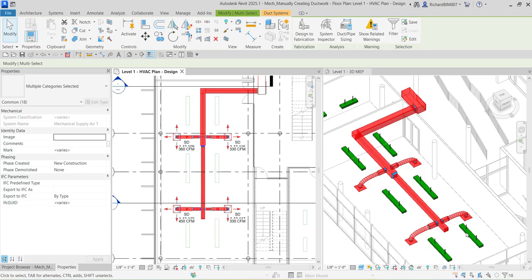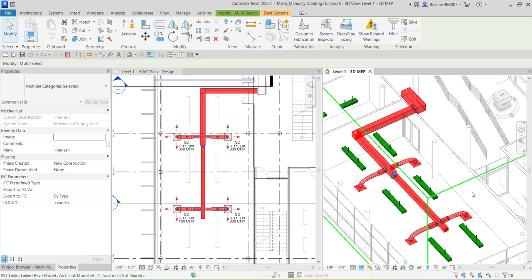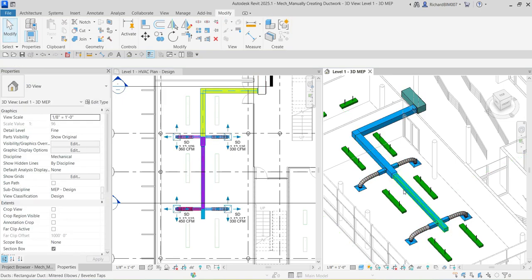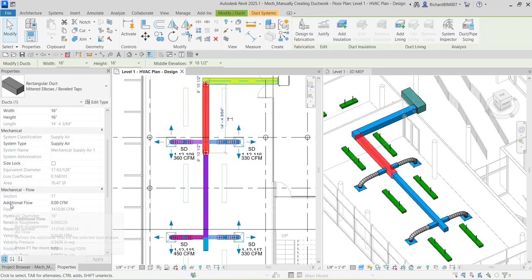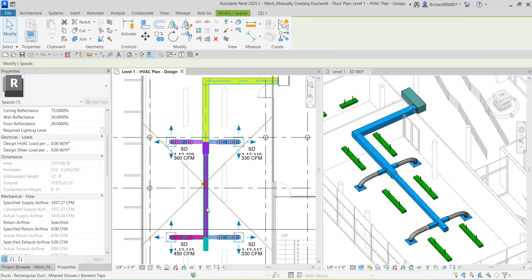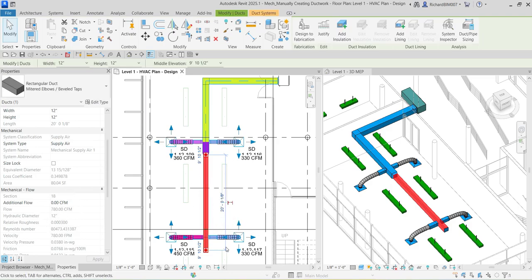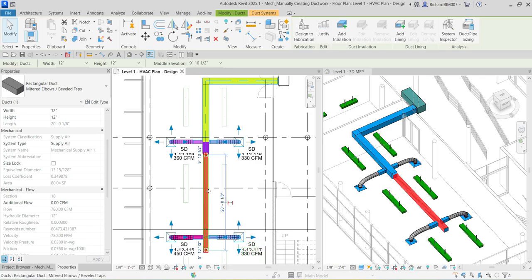The duct is now properly sized. Select Modify to deselect. You can verify by clicking the main duct — the flow is still 1470 CFM. Clicking the downstream duct segment shows only 780 CFM, because it supplies only two diffusers: 450 plus 330 equals 780 CFM total for that segment.